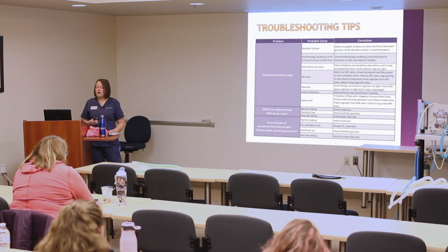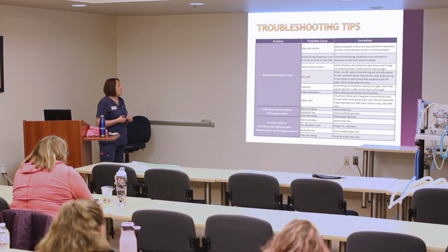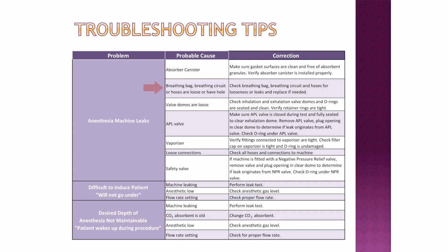So some troubleshooting tips. For machine leaks, I would say one of the first places to check is around your rebreathing bag. Holes get right around the neck there. That's my number one place to look. My number two place to look is the soda sorb assembly. If somebody changed it, they didn't tighten it down and cinch it in there very well. Valve domes can be loose. Make sure your pop-off is closed. Make sure your vaporizer is securely seated both at the inlet and the outlet.